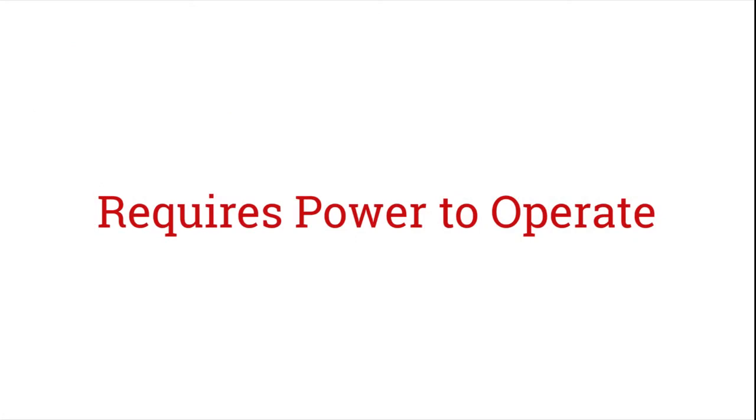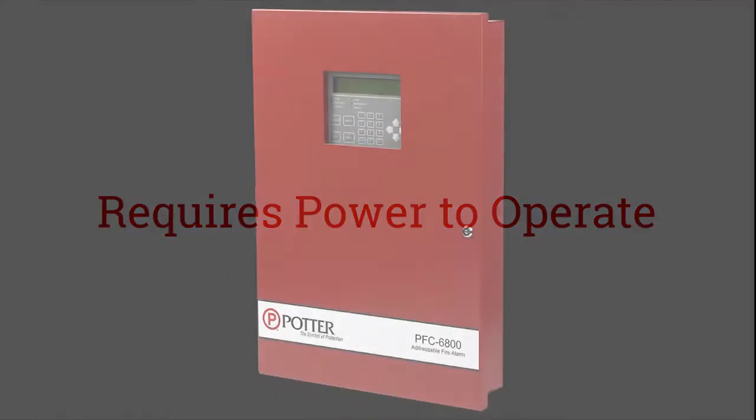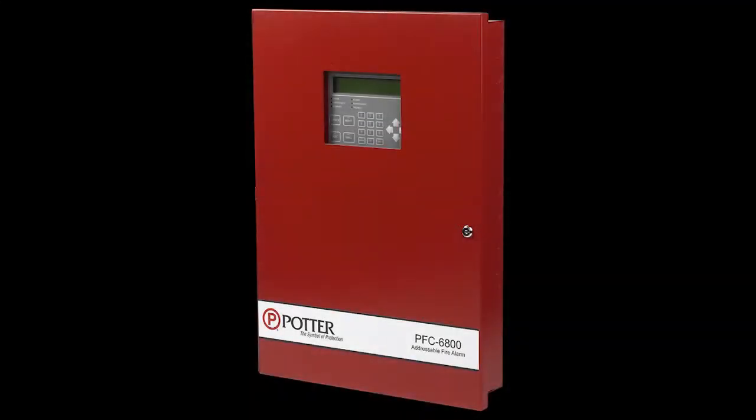The VSRAT requires 24 volt DC to operate and can typically be powered by the auxiliary power of the fire alarm panel or any UL listed power supply that provides sufficient battery backup. The device draws 20 milliamps in standby mode and 120 milliamps when in the auto test process.